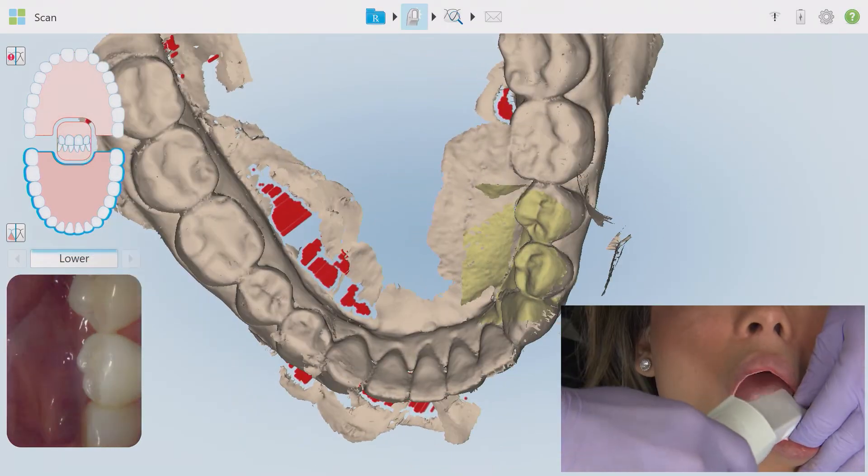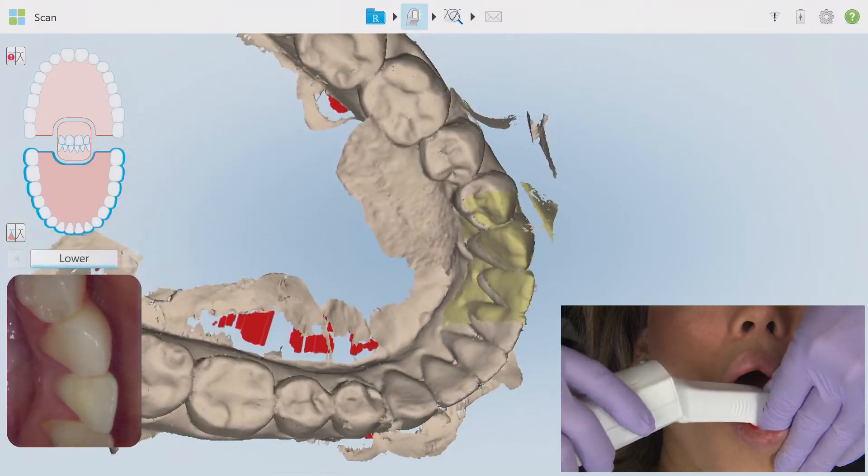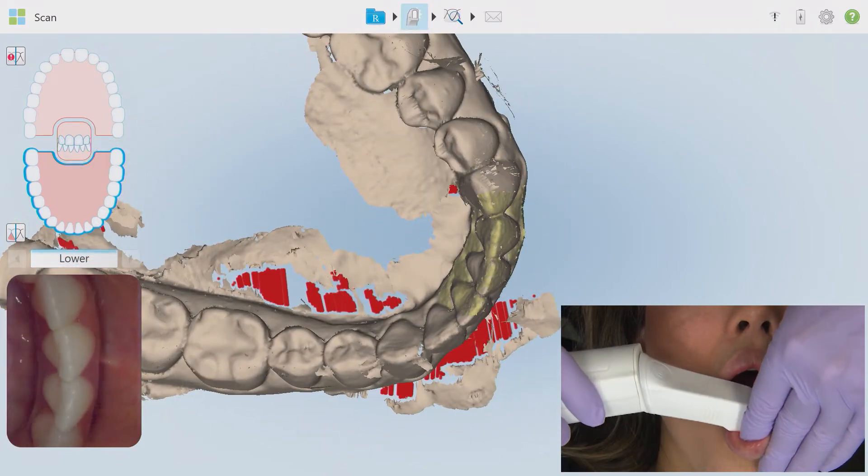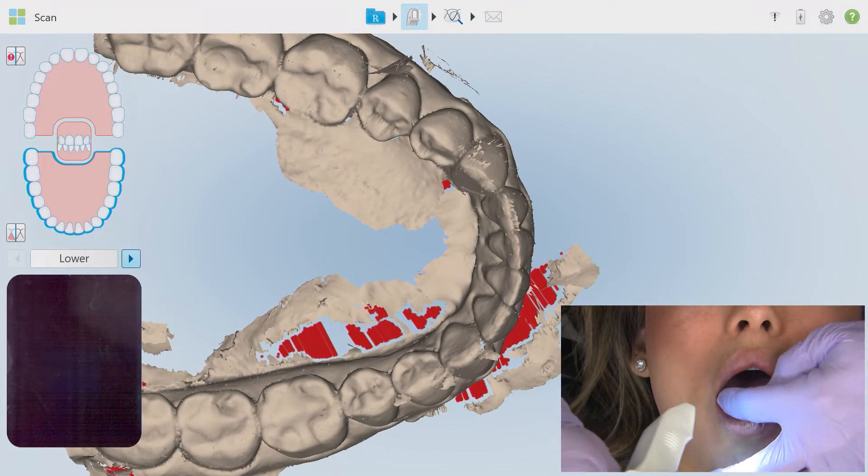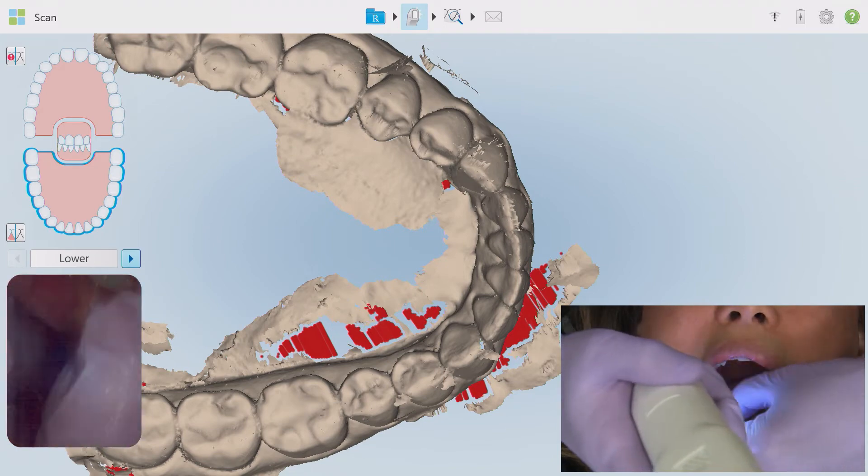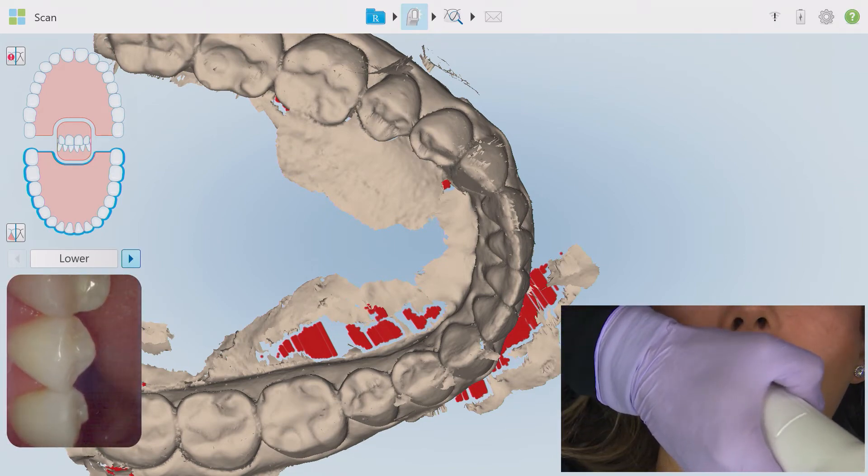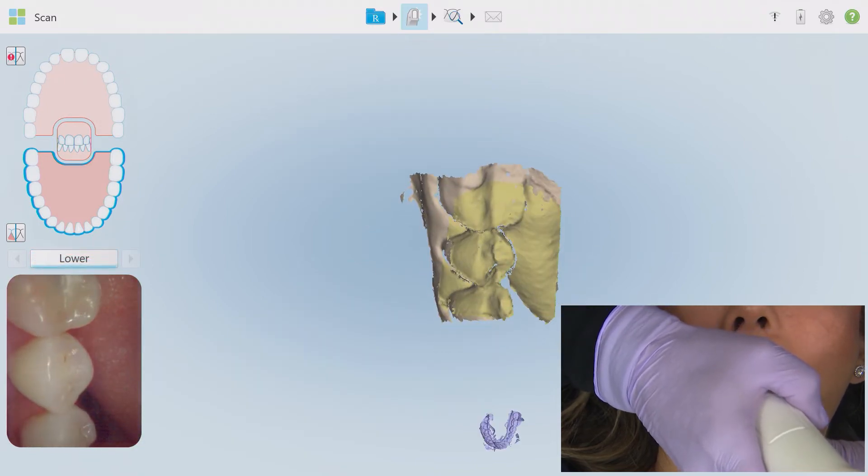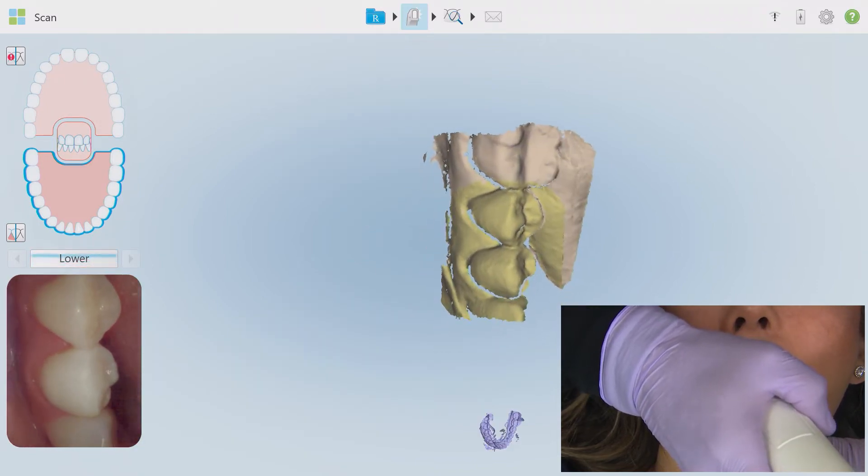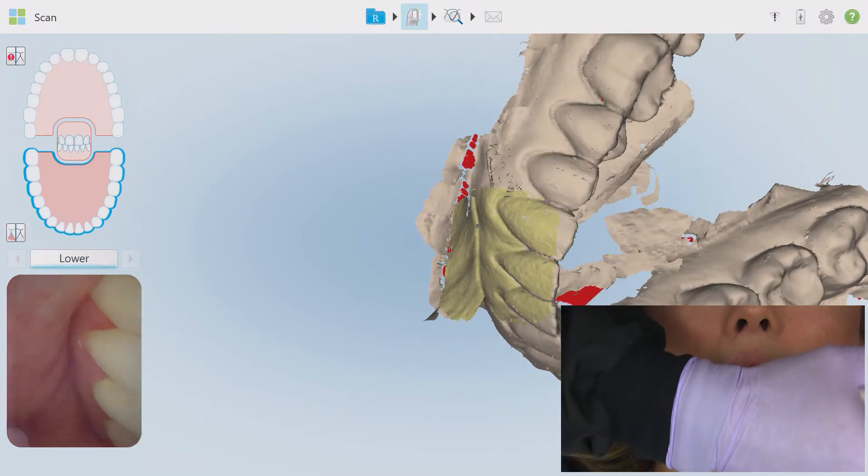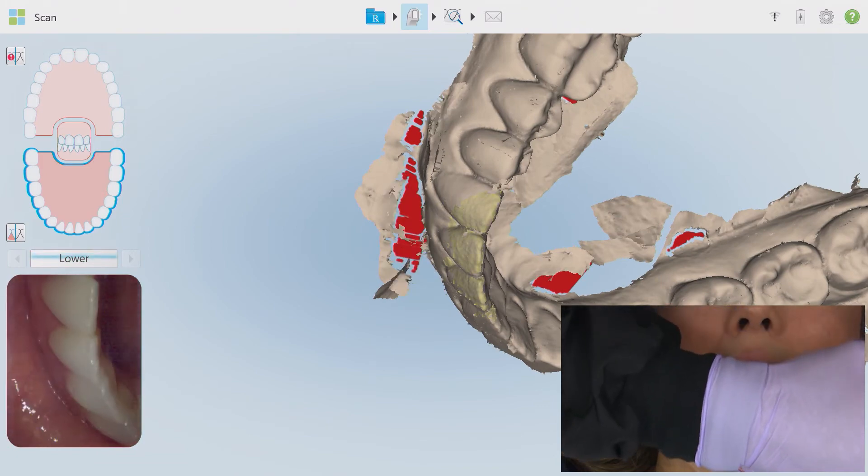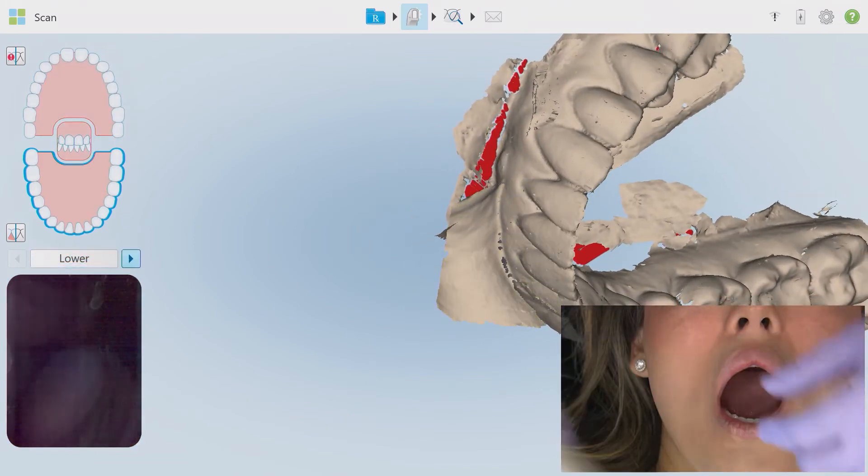The last bit of info that you need to scan for full arches are the incisal edges. You are always going to make this the last step after all other surfaces are completed. All we need to do here is rock the wand, buccal to lingual over the incisal edges, once on the right and once on the left to capture the edge details. Like I keep saying, I still want to start on a flatter posterior surface to help the wand mesh the scans together. Maybe just start on the bicuspids until the mesh happens and then rock the wand, buccal to lingual, moving towards the midline. Make this scan last no more than 3 to 5 seconds, and then review the final scan to make sure it's complete.